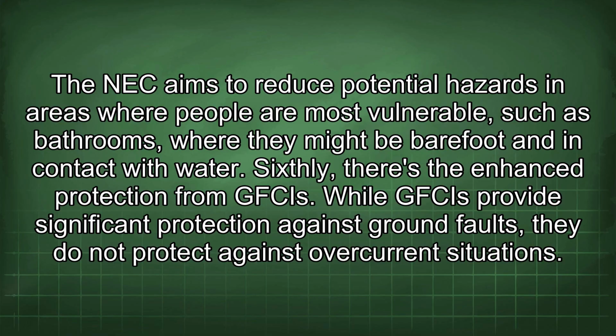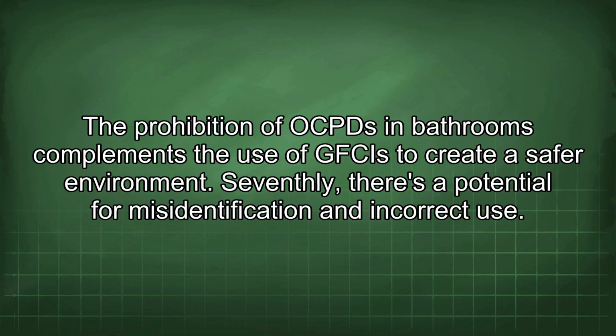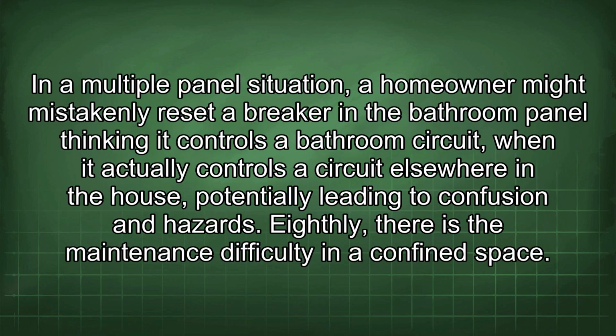Sixthly, there's the enhanced protection from GFCIs. While GFCIs provide significant protection against ground faults, they do not protect against overcurrent situations. The prohibition of OCPDs in bathrooms complements the use of GFCIs to create a safer environment. Seventhly, there's a potential for misidentification and incorrect use. In a multiple panel situation, a homeowner might mistakenly reset a breaker in the bathroom panel thinking it controls a bathroom circuit when it actually controls a circuit elsewhere in the house, potentially leading to confusion and hazards.